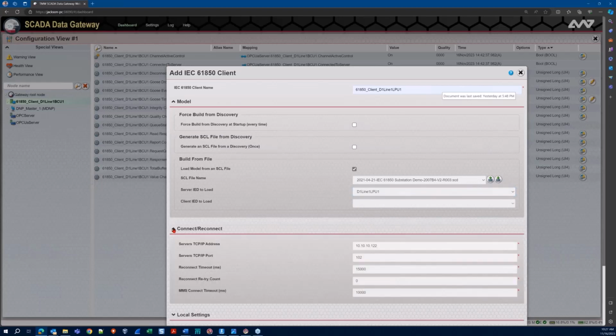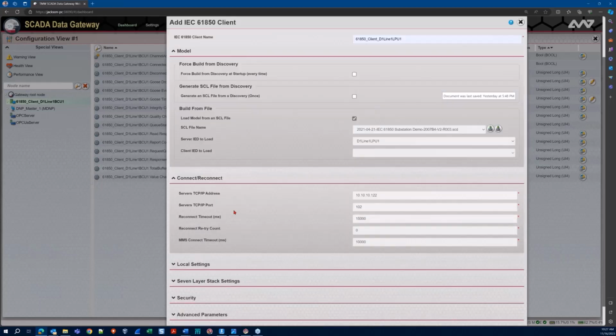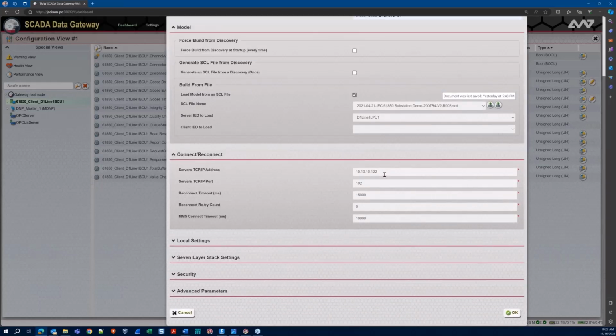One of the cool things this does for me is that because the SCD file contains the communication settings for the device I'll be connecting to, those are filled in automatically. I see the IP address already filled in, as well as other parameters like port.